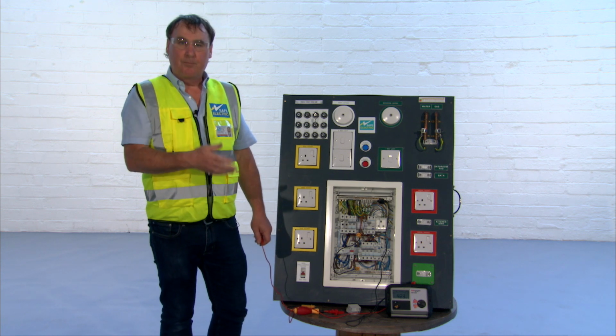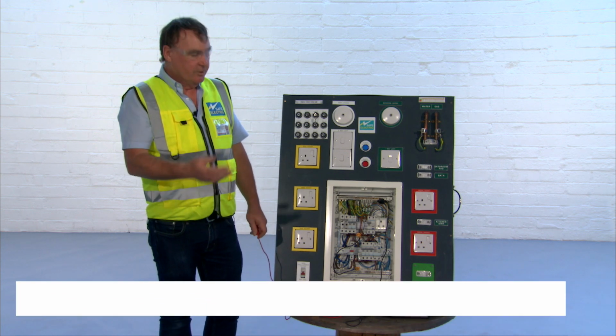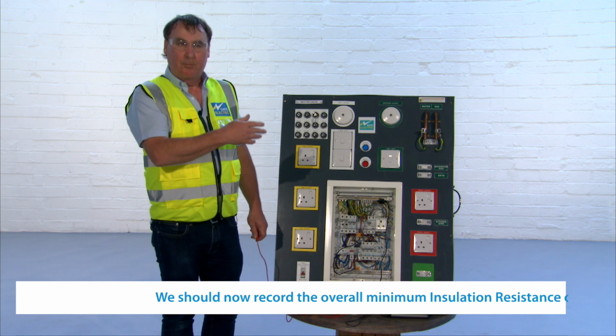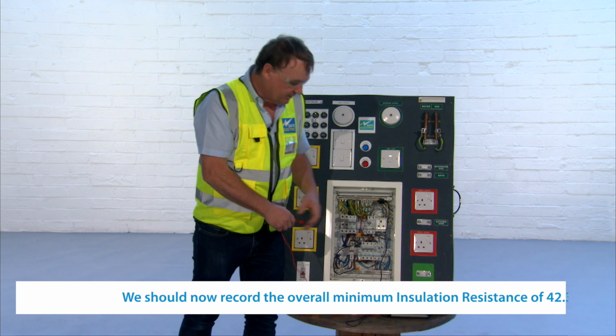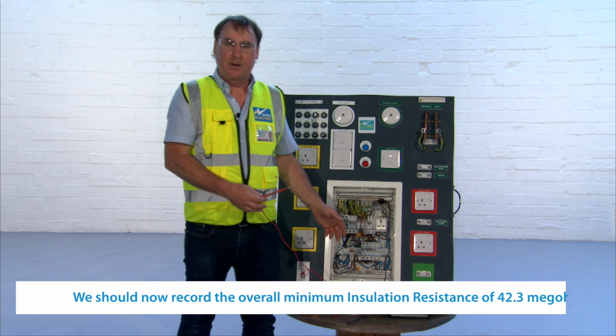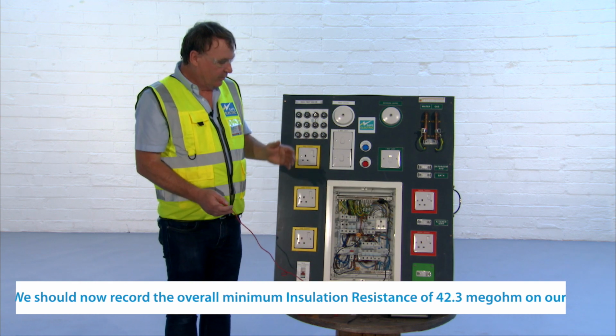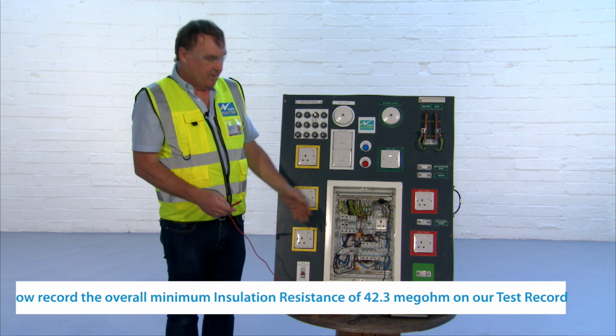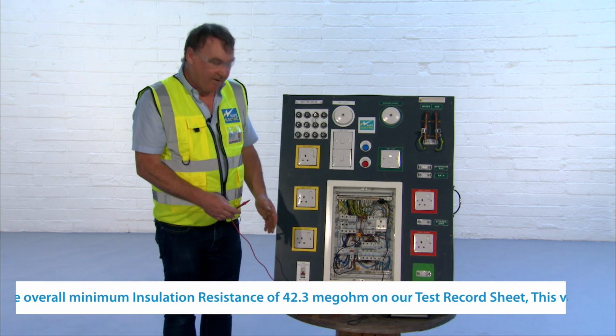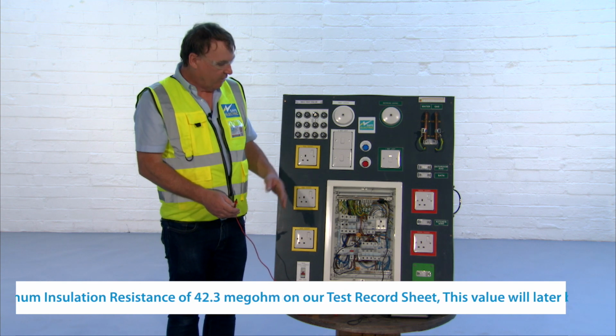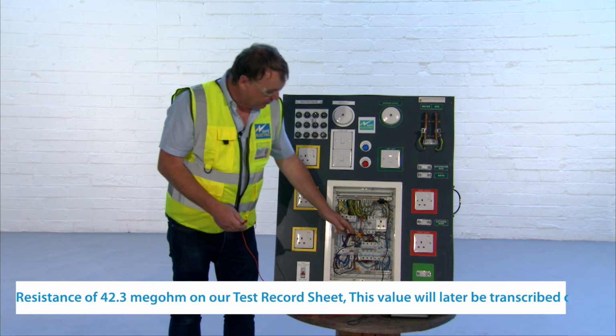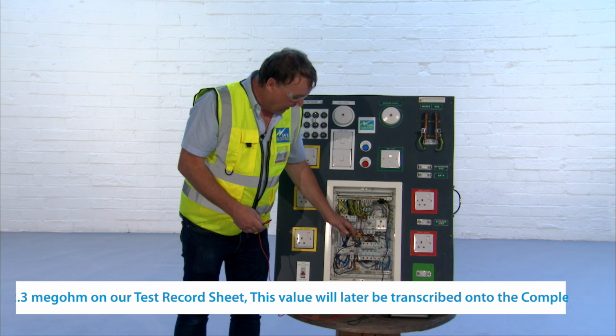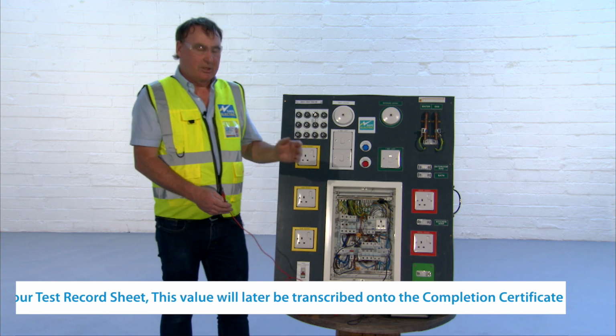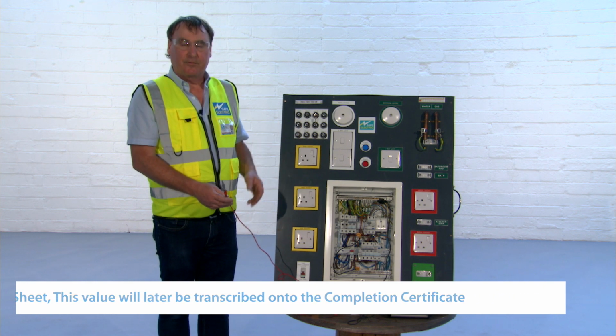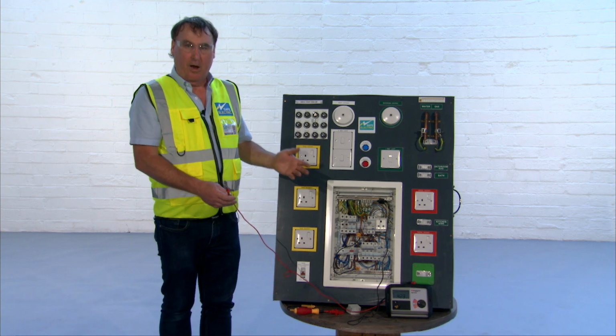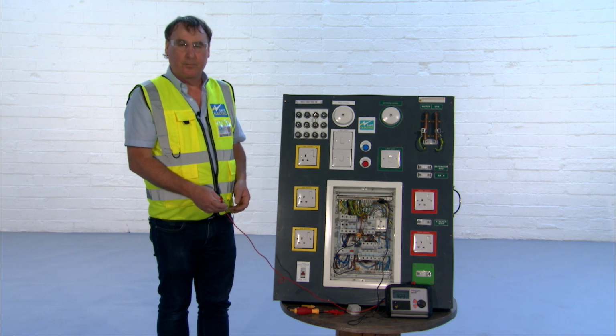Remember, the minimum is 1 mega ohm. So we've exceeded the minimum by 42 times. This is 42 million ohms separation between the lives and the earths. While carrying out this test, we have applied no voltage across any of our equipment because we have, in effect, shorted out the live and the neutral. So this is the recommended test for insulation resistance under IS 10101.